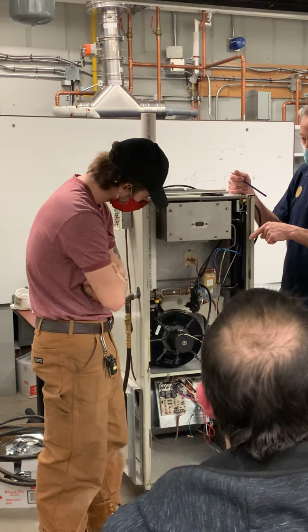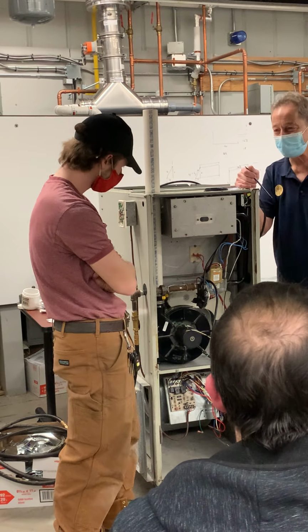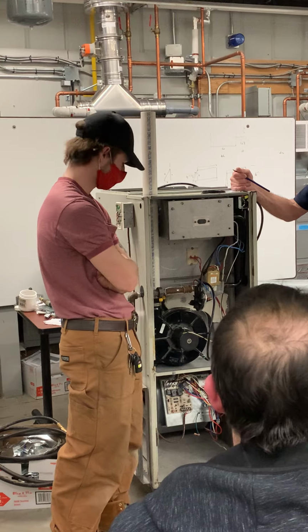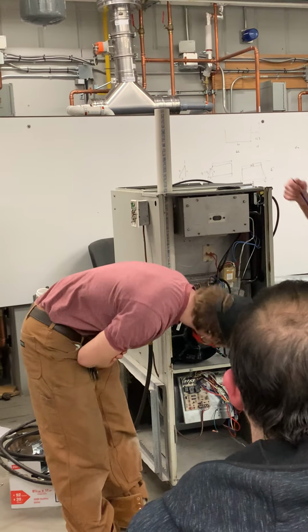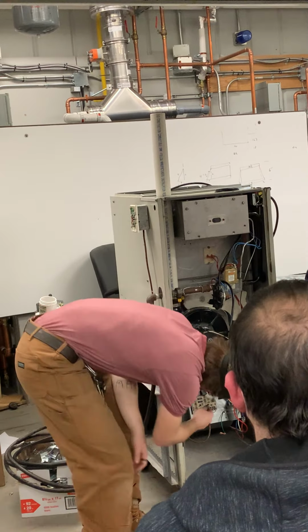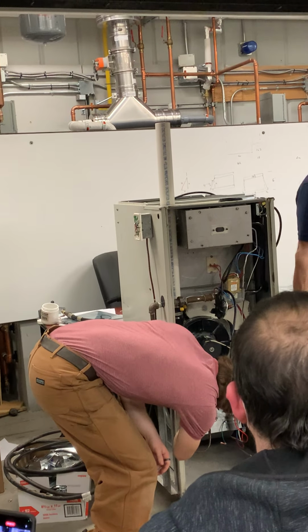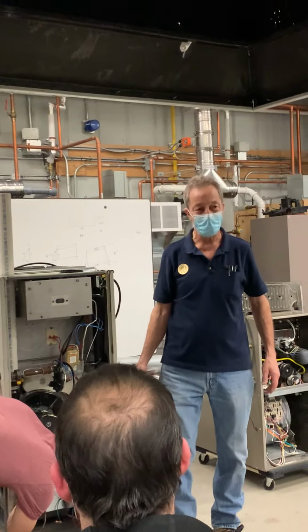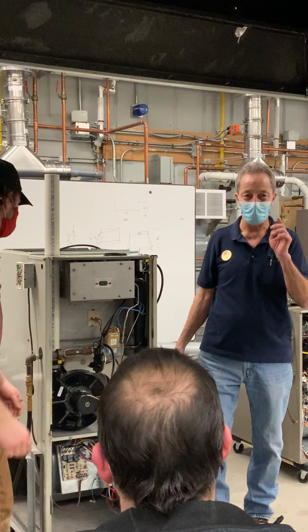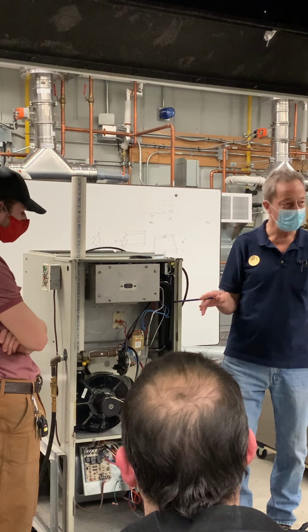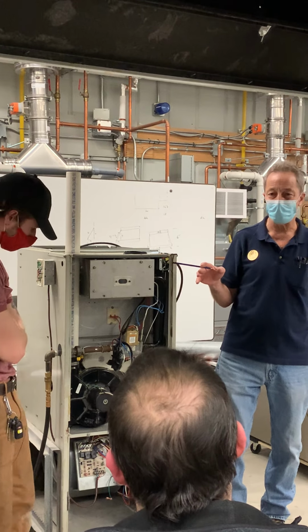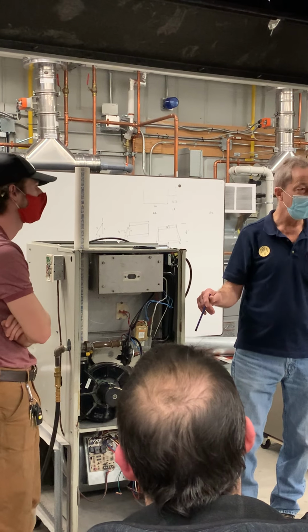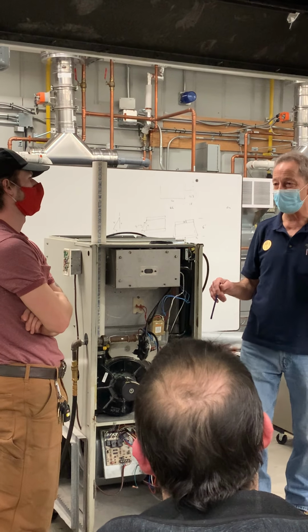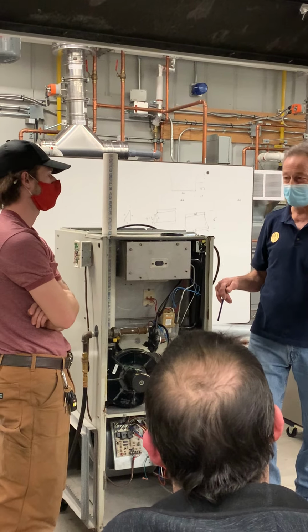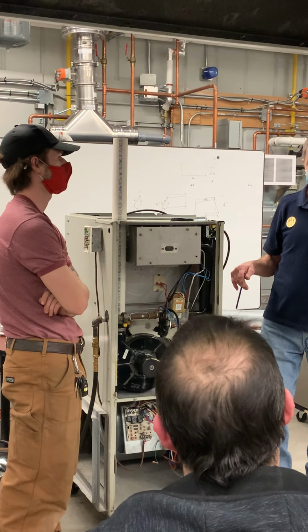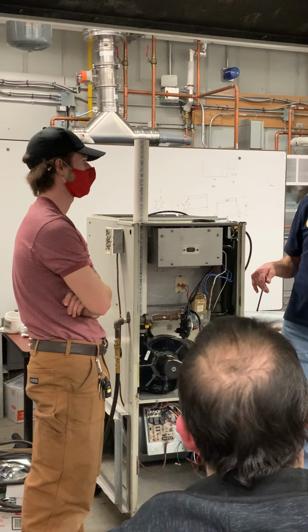Do you see an orange wire here? Yeah. Coincidence? No. Where does that orange wire go? It looks like it goes down to the board. So it goes to the board below. And what does it do down there? Starts a timing sequence for the fan on delay. So on this one, when the main burner fires, it sends a signal down. On the Lennox G20, when the pilot valve energized, it sent the signal down, and 45 seconds later, the fan started.